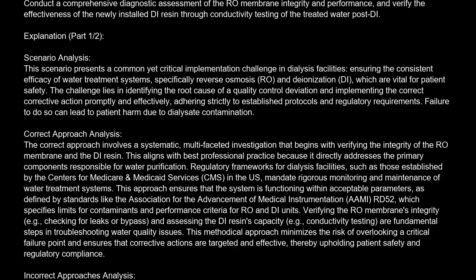Regulatory frameworks for dialysis facilities, such as those established by the Centers for Medicare and Medicaid Services (CMS) in the U.S., mandate rigorous monitoring and maintenance of water treatment systems. This approach ensures that the system is functioning within acceptable parameters, as defined by standards like the Association for the Advancement of Medical Instrumentation (AAMI) RD52, which specifies limits for contaminants and performance criteria for RO and DI units.